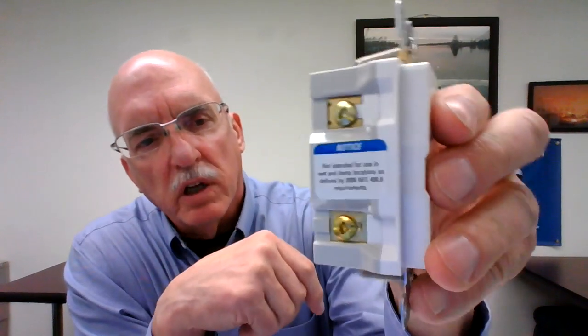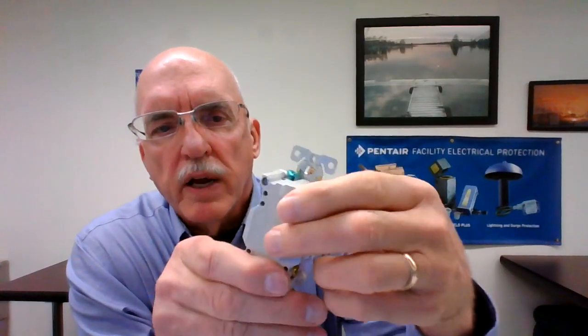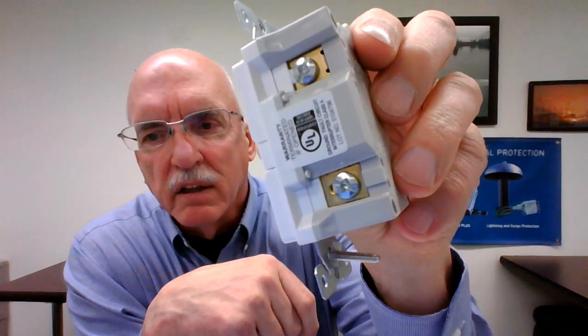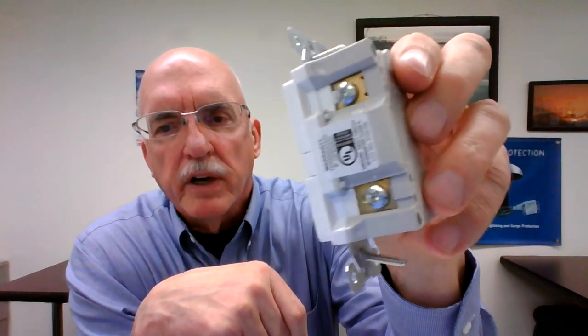There's two different colored screws on the sides of the receptacle. I'll talk about this in an upcoming session. But the ungrounded hot terminal right here is a brass color, all right? The grounded neutral side on the other side is a light silver color. And the correct way to connect these GFI receptacles is to connect the black wire to the brass colored screw and the white insulated wire to the light colored screw. So saying black to brass and white to light is something I've used all through my career and anybody I've had to teach. Black to brass and white to light is an easy way to remember what color insulation goes where.